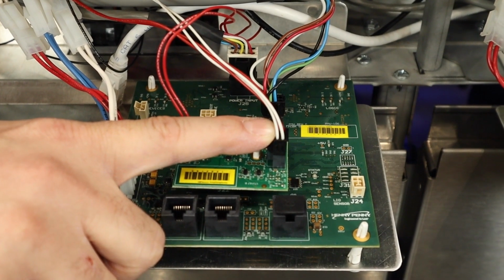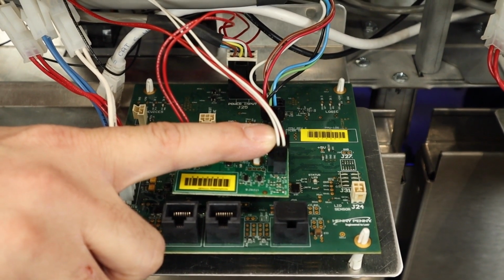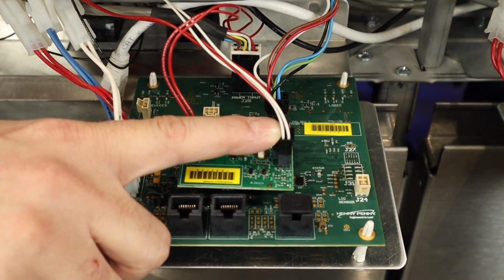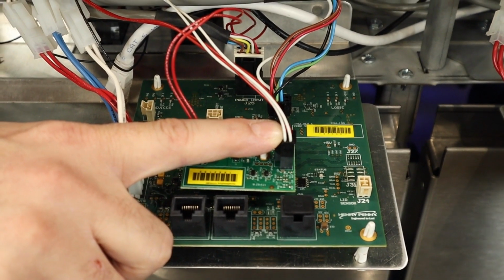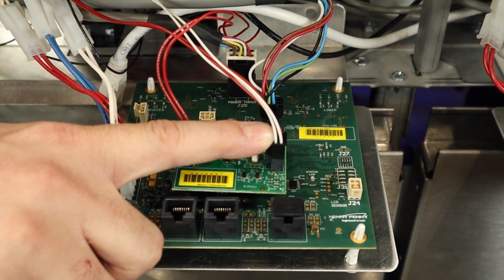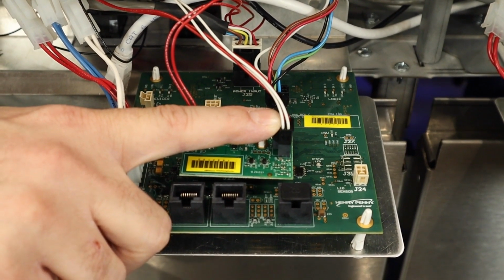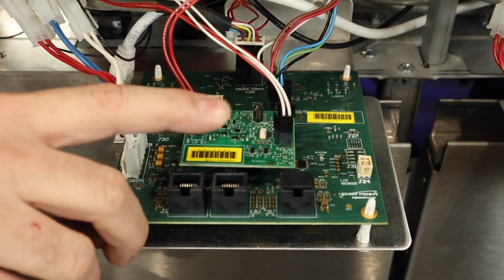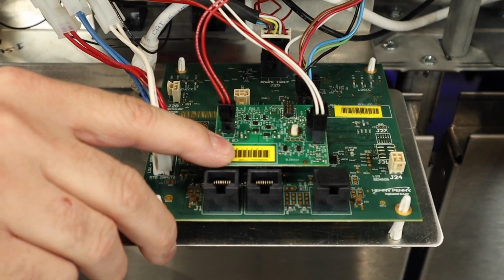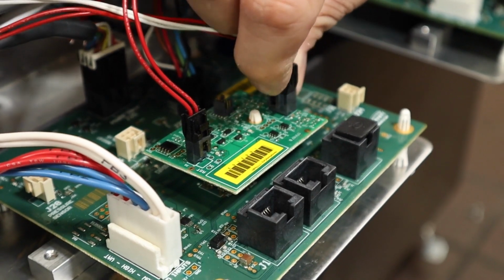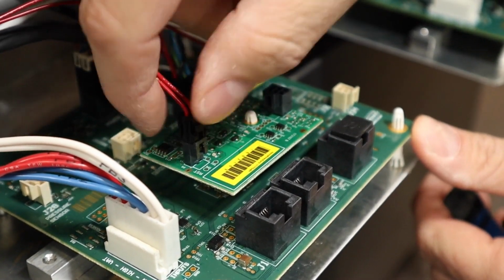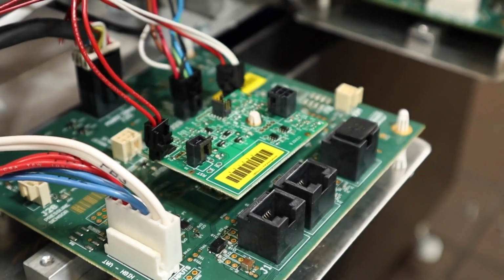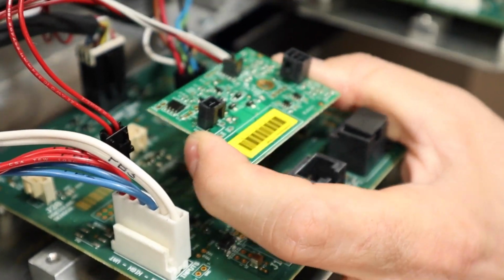If the probe is found to be off and out of calibration, then we can proceed with replacing it. If the probe checks good, and both probes for full VATs, then we can assume it is our high limit PCB board that is faulty and we can replace it. This PCB is replaceable separately from the PMU board.